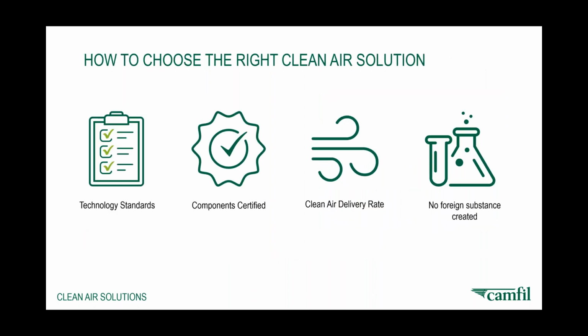And choose that solution according to the relevant technology standards and the relevant air filter test standards. Ensure that all components are certified, whether in the filter or in the air cleaner, for use in the environment, whether it's a hospital or a restaurant or a general office environment. Ensure the components are certified for use in the correct environment. Ensure that the number of air changes or the clean air delivery rate is correct. And again, REHVA have made recommendations between 2 and 5, so ensure you can actually deploy the correct amount of air cleaners to get between 2 and 5 air changes through the HEPA filter.